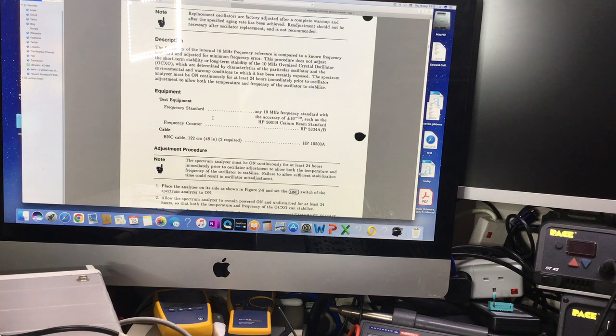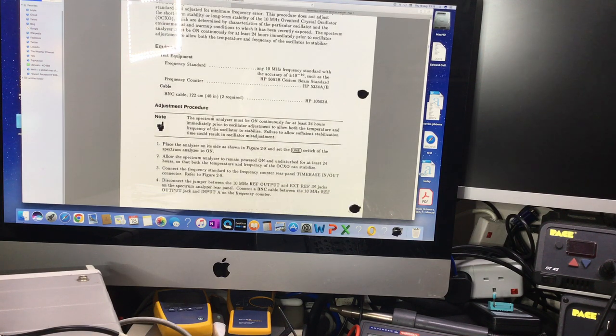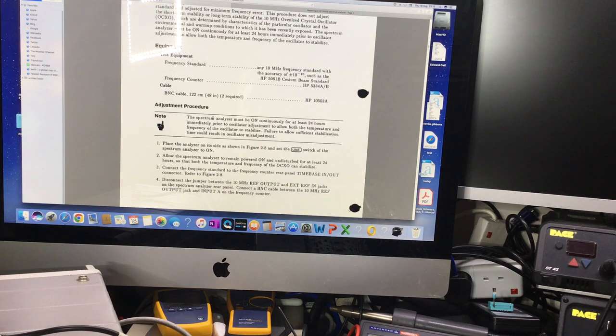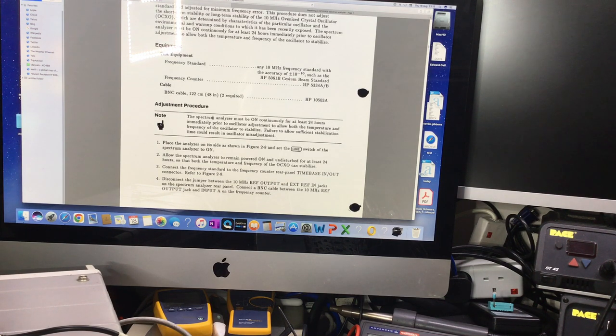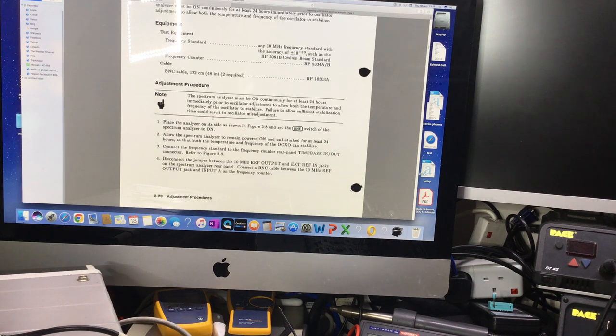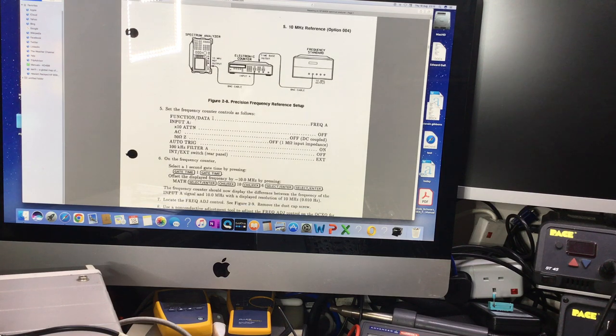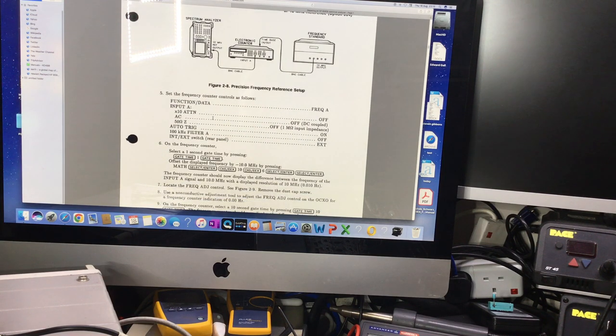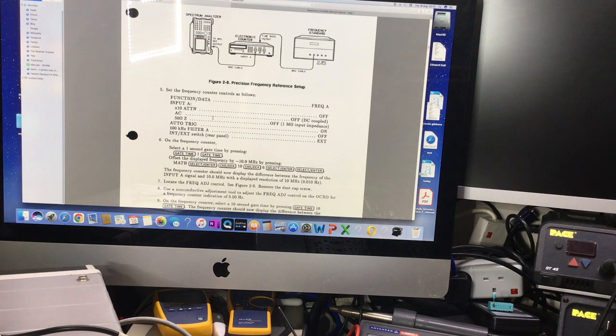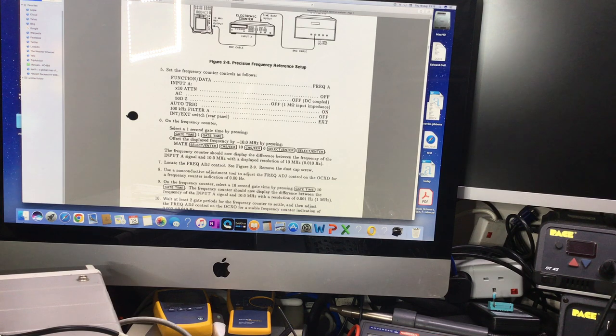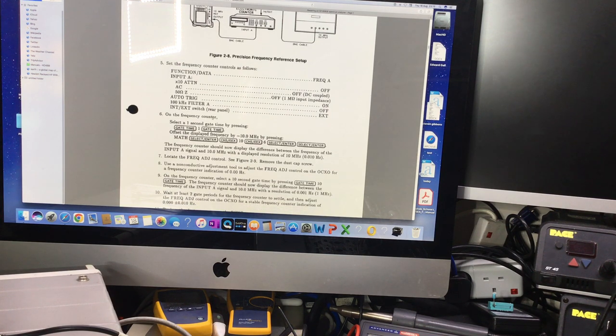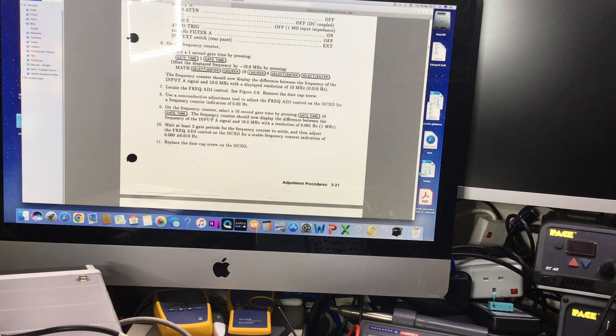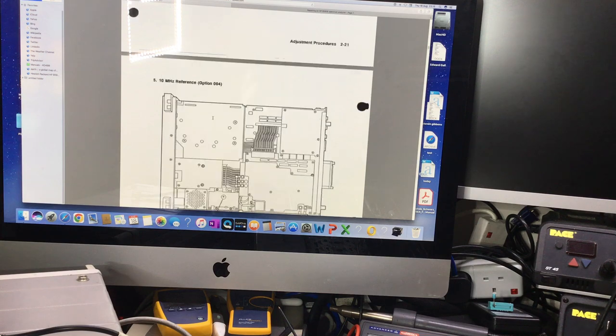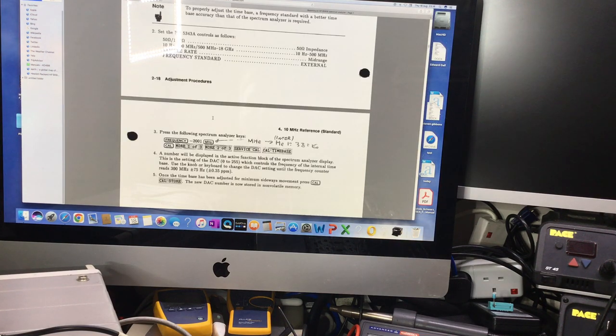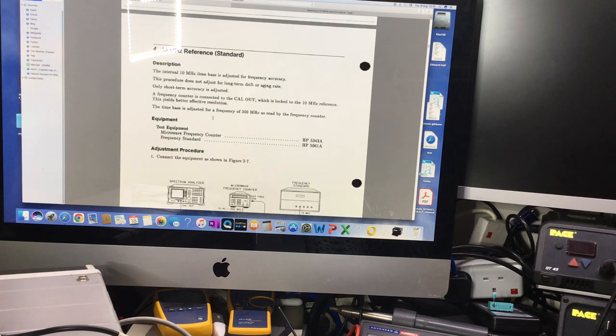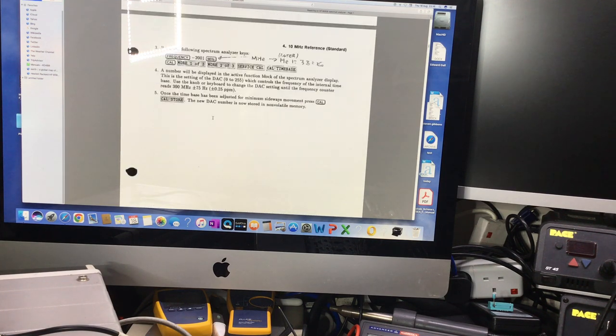So then it talks about option 4, which is a TCXO that's got its own procedure here. Time base in-out connector. Disconnect the jumper on the 10 MHz reference output and connect a BNC cable between that adjustment procedure. And that one then talks about select gate time, select frequency 10 MHz by pressing this. The frequency counter should display the frequency, locate the frequency adjust control, which this one doesn't have because it's not got option 4. So that's irrelevant, because that talks about that little fine tune thing. So basically we're back to where we were, which is the 10 MHz standard. So I'm following that now.